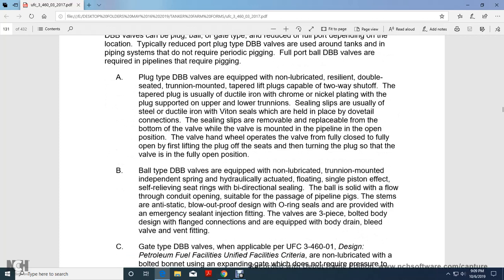Plug type double block and bleed valves are equipped with non-lubricated resilient double seats with a trunnion-mounted, tapered, lifted plug capable of two-way shut-off. The tapered plug is usually ductile iron with chrome nickel plating, with the plug supported by upper and lower trunnions. Sealing slips are usually ductile iron with a Viton seal held in place with a dovetail connection. The seal slips are removable and replaceable from the bottom of the valve.